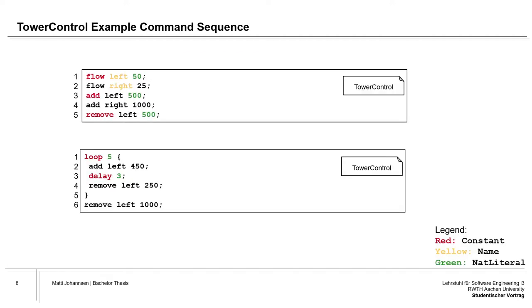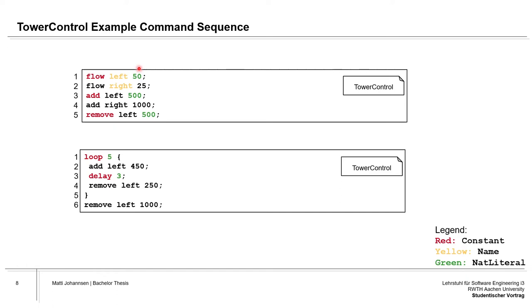We're coming over to two examples of the domain-specific language. First of all, we have syringe operations which here is a flow, add, and remove command. They all start with a constant, and afterwards they have a name here which is a string and represents either the left or the right syringe. Lastly, they have a natural literal. In the case of the flow, it represents the speed of acceleration, which means with which speed the syringe aspirates or dispenses fluids in microliters per second. For the add and remove command, it represents how much volume is added to the syringes.